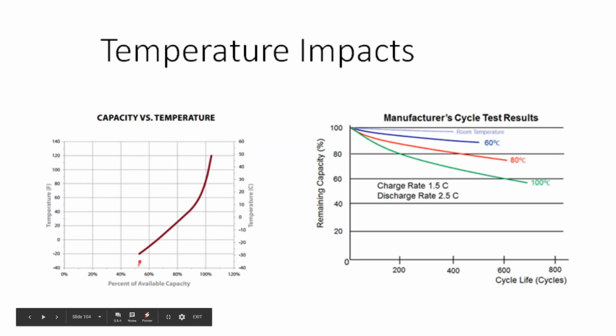Now, the battery can take below freezing temperatures, but only when it's charged. If it's completely discharged, the electrolyte can freeze. If it's charged up, the electrolyte won't freeze even below freezing point. And so what that means is in the wintertime, if your batteries are outside in a box, you can't have them get below freezing and be discharged to more than 50%. At that point, the electrolyte begins to freeze.